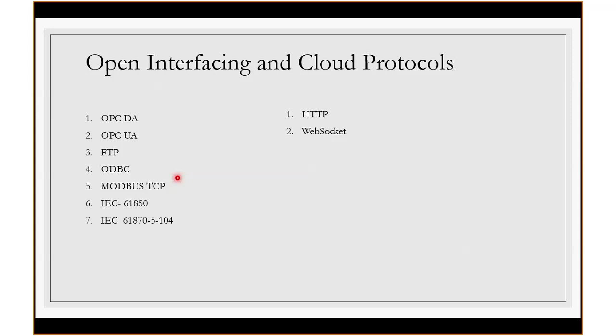So the fifth one, I'm just covering other three protocols that may not be used for a regular WinForm application, like data sharing to things. But most of the devices like meters and multifunction controllers still use Modbus TCP because of the simplicity. Most of the TVM meters, trivector meters, multifunction meters and multifunction devices are still supporting Modbus because of this simplicity. You can poll the data over TCP/IP network and fetch it, and the payload is very small, so it's quite a fast protocol. You can get the data in milliseconds. If you send a query to fetch 50 bytes of data, you will get that data in 50 milliseconds, so just assume how fast it is. That's why Modbus is still familiar in most industries in India as well as other parts of the world.